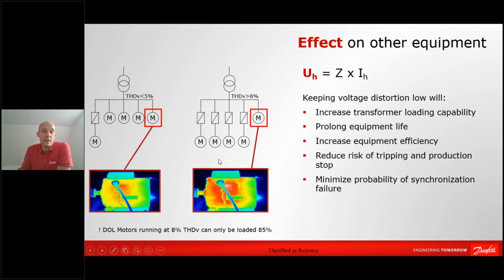If you take another scenario where you have now added more drives to your installation, you can see that the voltage distortion increases. So now the voltage distortion went up to 8% because you added more drives that distort the current more. And when you have more current distortion, and Ohm's law says that the voltage distortion depends on the current distortion times the system impedance, then that means simply that now the direct online motor is seeing a worse voltage signal.